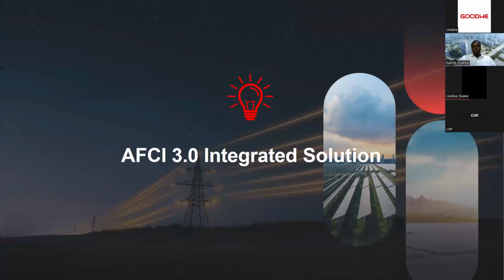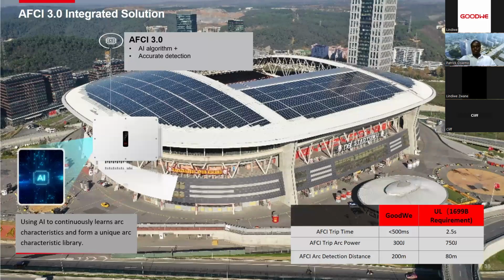Now with the AFCI, the Arc Fault Circuit Interrupter version 3.0 solution, in case you'd like to monitor any arcs on your PV strings, the arcs might be due to leakages of lightning surges to the PV modules, or even loose connections on the MC4 connectors. With the AFCI integrated, which is AI, it's able to learn the arc curves of the various surges on your strings and detect how fast it's going to respond. The algorithm we've included in our GT series is very fast responding. As you can see with GoodWe, our AFCI trip time is less than 500 milliseconds, contrary to the UL standard, which approves a response trip time of up to 2.5 seconds.